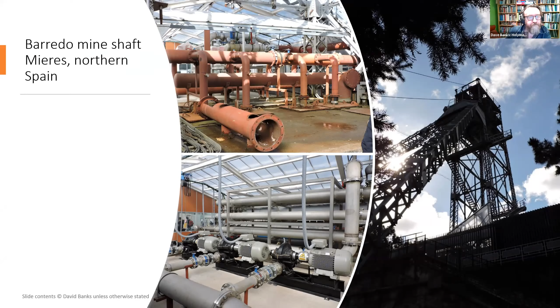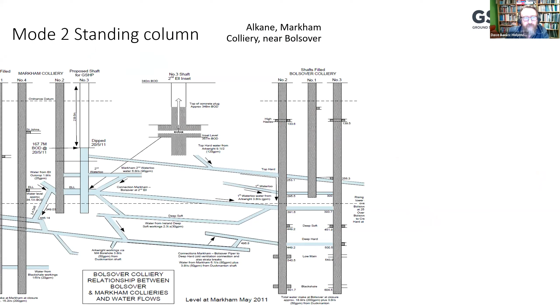The second way of getting heat out of mine water is a kind of standing column arrangement. This has been tried by a firm called Alkane, now known as Infinis, who have a site near Bolsover in Derbyshire at the old Markham mine. They've got a little 20 kilowatt heat pump which they use to heat their offices there. What they've done is put a small submersible pump down the mine shaft nearby, take a couple of litres a second from quite a long way down, take the heat out of that water, then re-inject the water somewhat deeper into the same shaft, and it works.